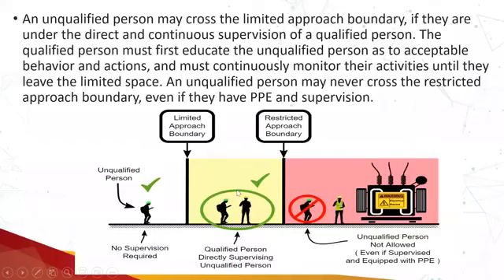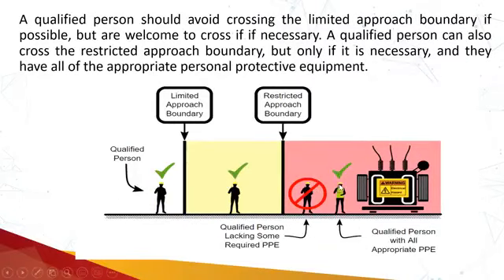They are not performing any task within this boundary, but they might have to cross those boundaries, so it is a requirement that they must be escorted by the qualified person. When a qualified person is within the restricted approach boundary, he should be wearing all the appropriate personal protective equipment, and if the task requires it, he should have an energized electrical work permit. So he will be holding that permit as well. Any questions up till now?